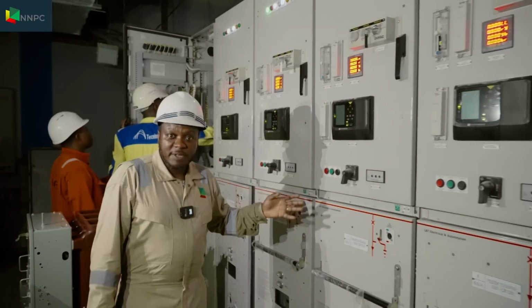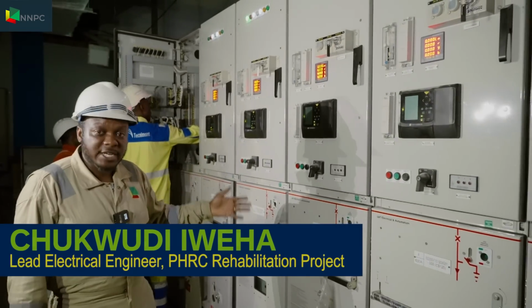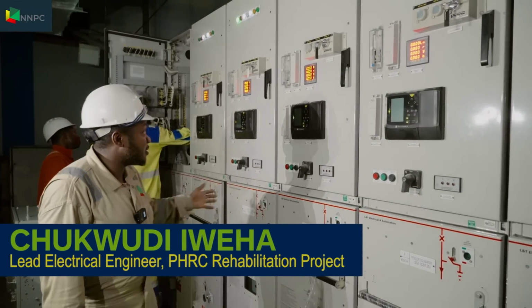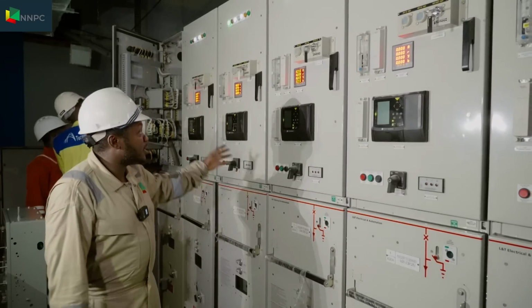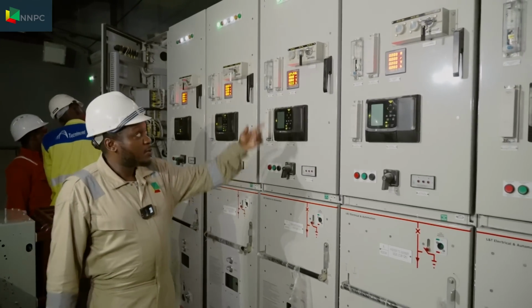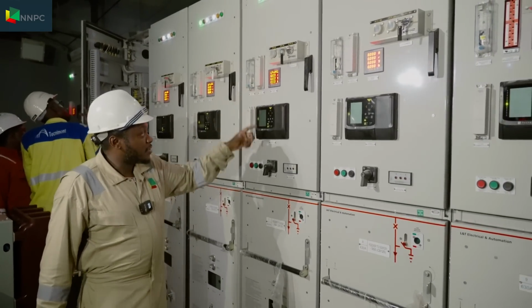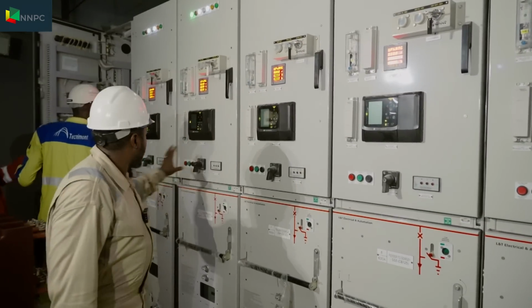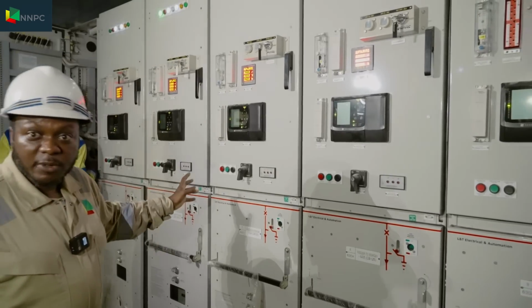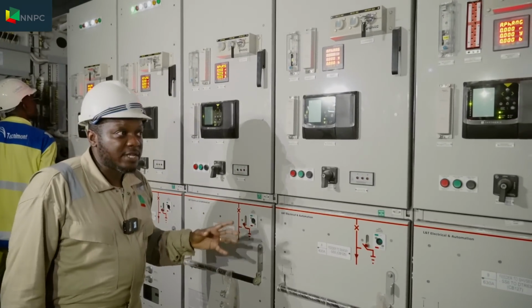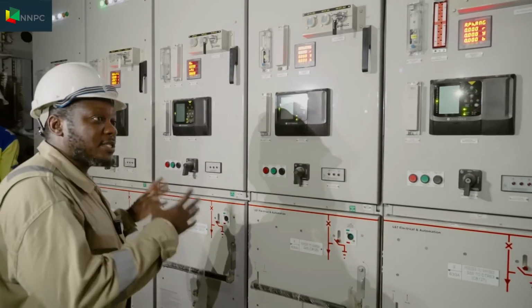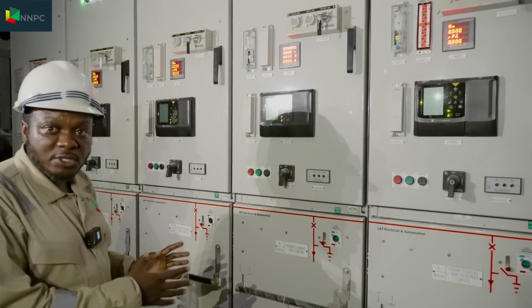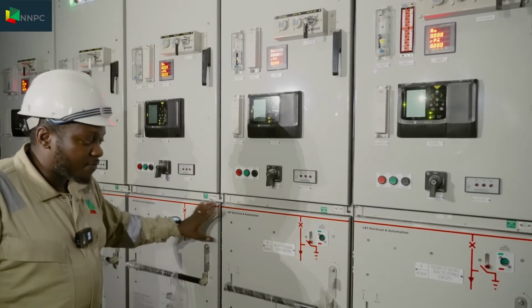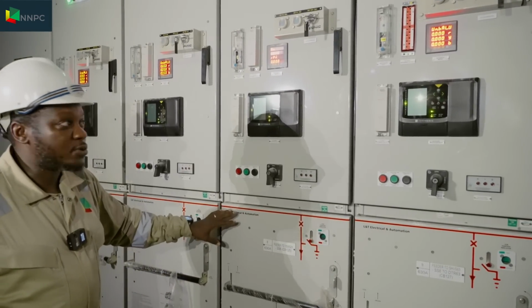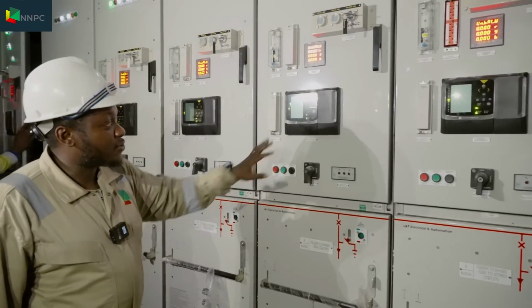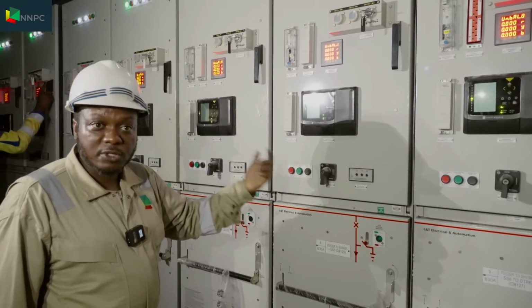We can see we have energized. As I said, we'll be energizing in a few weeks. We have energized this particular switchgear, and these indicate the protection relays. You can see the red, yellow, blue, and we are doing some final checks because safety is key to make sure that everything is working. This is the high voltage switchgear with the vacuum circuit breakers. It's an L&T product. The vendor has come, he has already programmed the HMI, which you saw was on in the other one.